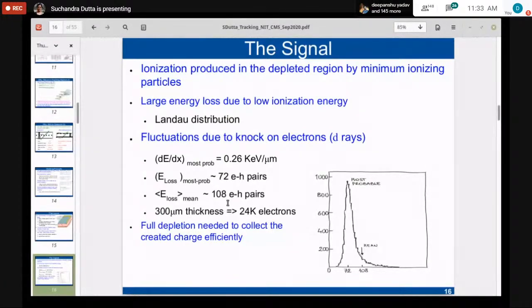And the charge which is created, let's say the 24,000 electron hole pairs, we need to fully deplete the device. So we have to apply the voltage up to a level so that the detector is free of its majority carriers, because we don't want the electron hole pairs created by the passage of the particle to mix with the intrinsic electrons, the space charge in the detector, and that's why we need to deplete it fully.